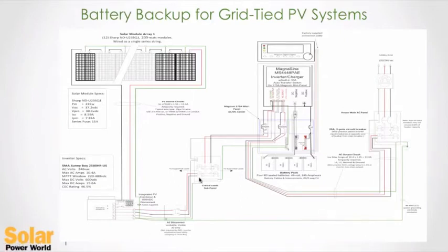Okay, I'm back up. So it takes about 30 to 50 milliseconds usually for this switching, disconnecting from the utility and then powering up. Probably our grid-tied inverter will notice that lag, and it will probably do a standard 5-minute timeout because of that. Depends on how the utility fails, but it's typical that we will do a 5-minute timeout, and then if the sun is shining, it'll come back up again. If the sun isn't shining, well, we still got the stored energy in the batteries, and we'll support our critical loads.